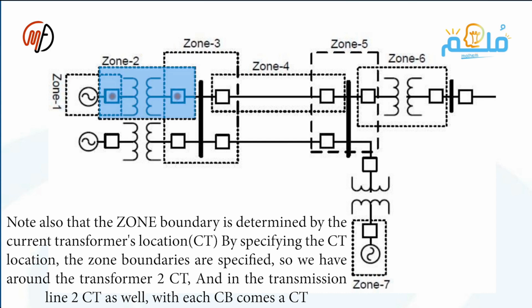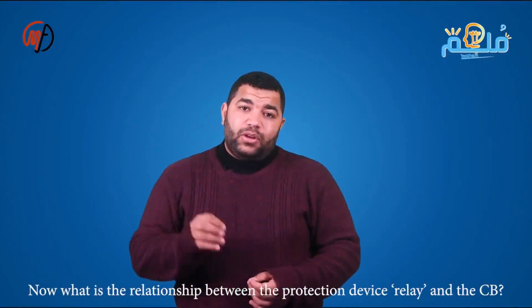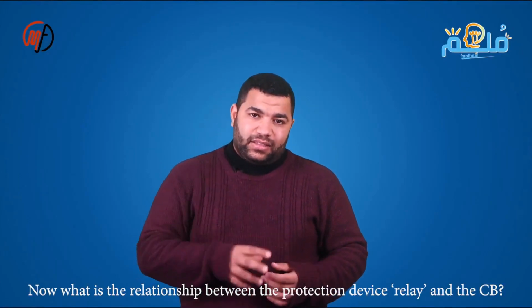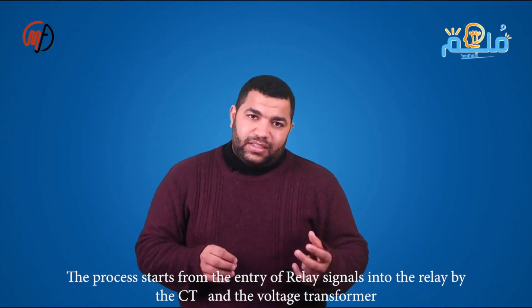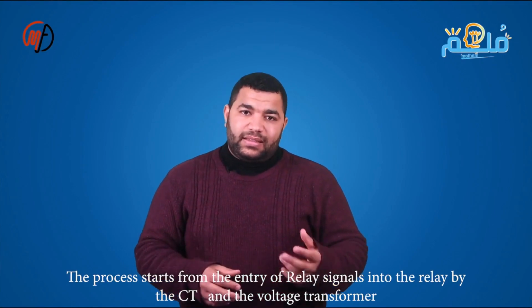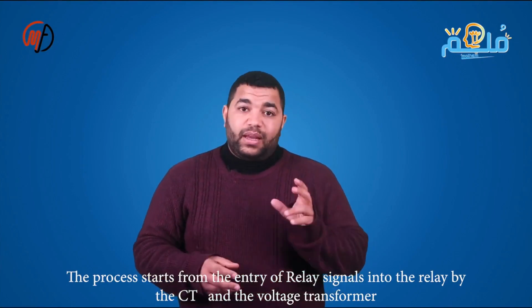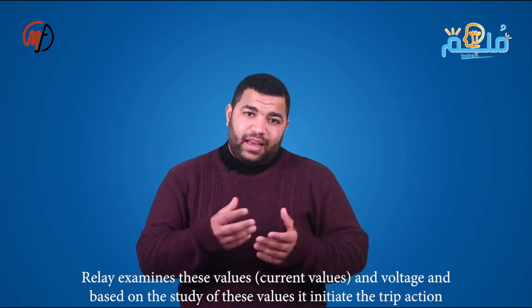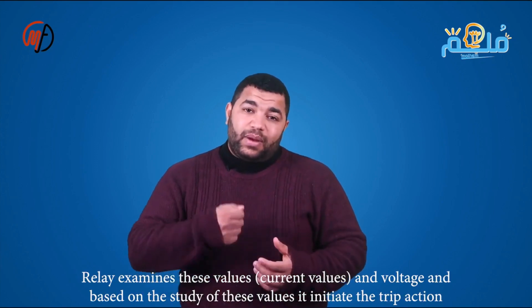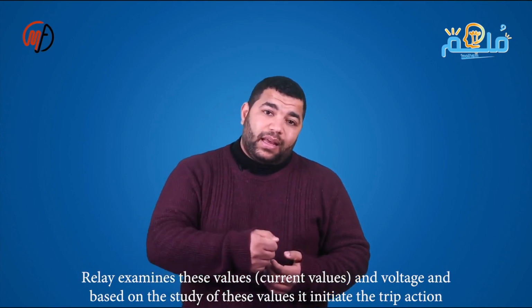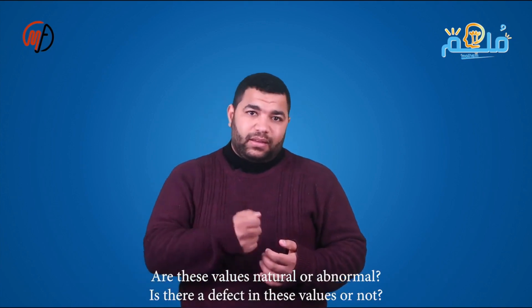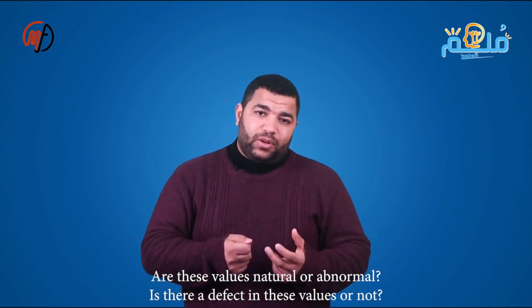What is the relationship of the protection device, the relay, and the circuit breaker? It starts with the relay getting signals from the current and voltage transformers. The relay analyzes these current and voltage values to decide if they are normal or faulty. It then sends a trip signal to the breaker, as shown in the diagram. In this diagram, there is a 3-phase bus bar, red, yellow, blue. From red, yellow, and blue, feeders come through the breaker. The breaker is symbolized in ANSI code as 52.